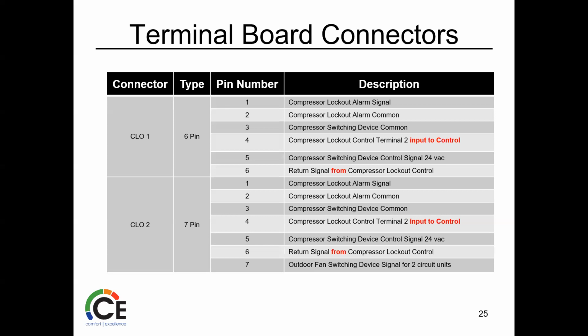5 at that point will send it through high pressure, low pressure. And again, we'll hit this again. And then as long as all that's satisfied, it comes back to 6. 6 sends it to the contactor. So if you think your CLO may be bad, the easiest way to test this is to jump 4 to 6. If the contactor comes on, then you've got something, a bad switch, a bad high pressure or something. Super simple to diagnose those. The only difference in a 2-stage is you'll have that second CLO, and then that has a terminal 7, which sends a signal to ramp up the outdoor fans.